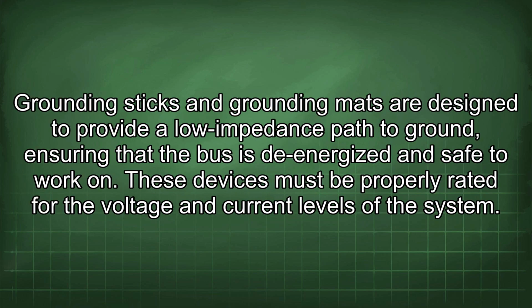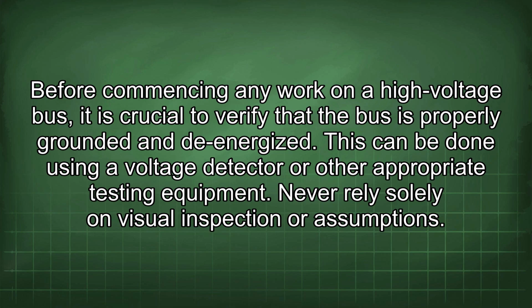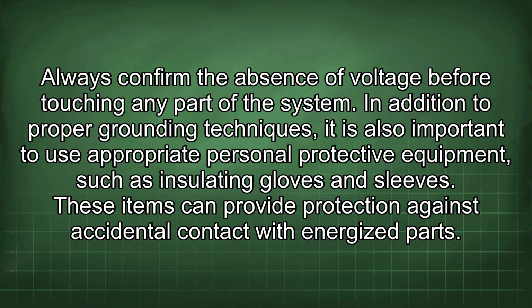Grounding sticks and grounding mats are designed to provide a low-impedance path to ground, ensuring that the bus is de-energized and safe to work on. These devices must be properly rated for the voltage and current levels of the system. Before commencing any work on a high-voltage bus, it is crucial to verify that the bus is properly grounded and de-energized. This can be done using a voltage detector or other appropriate testing equipment. Never rely solely on visual inspection or assumptions. Always confirm the absence of voltage before touching any part of the system.